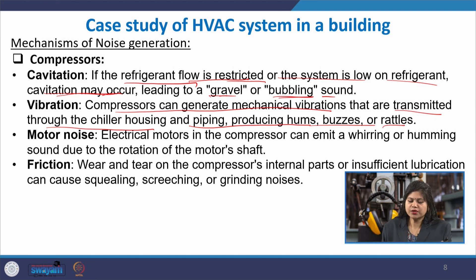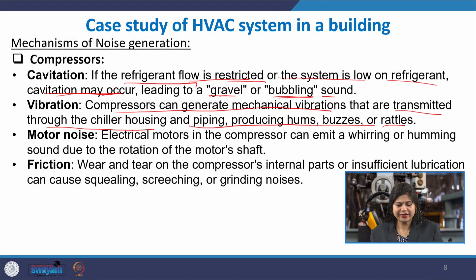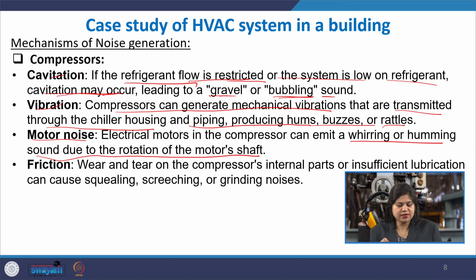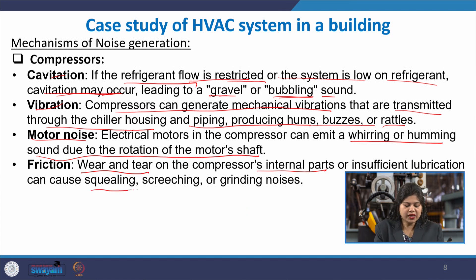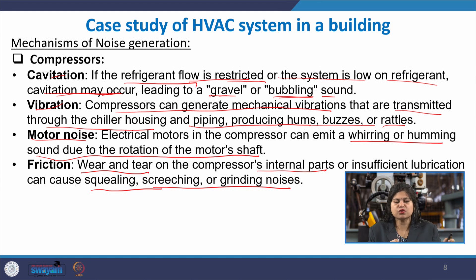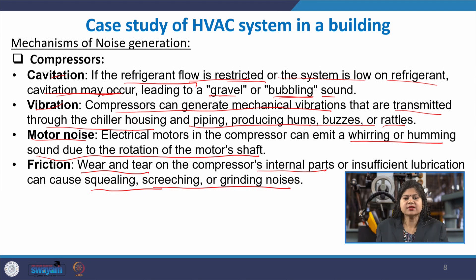Another noise source is motor noise from the electrical motors in the compressor. Because it is a mechanical system, parts degrade over time with surface roughness, and contact between worn internal parts causes squealing, screeching, or grinding noise. This friction-based noise indicates the compressor is aging — parts are worn out and insufficient lubrication is causing friction.